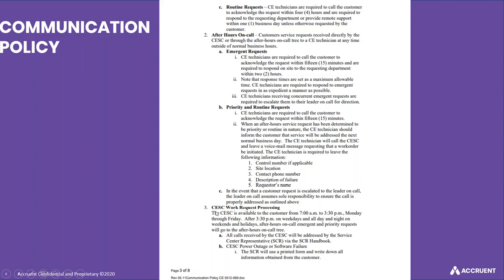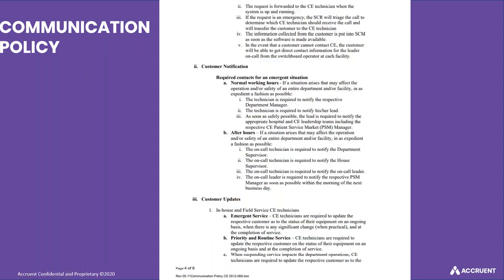And then we had a process for the clinical engineering service center where people would call in, and this was our mechanism to make sure that everything was time stamped. At the time, our CMMS didn't have the ability to do that. Our computerized maintenance management software didn't have the ability to do that. So we developed a centralized call center that everyone would call into, and they had the ability to dispatch that call to the right person. Every device in our inventory had a primary, secondary, and tertiary technician assigned to it, so that we could make sure that the right person with the right set of skills was always responding to these calls, and they were also broken out by geography, again, to make sure that the closest person got to those calls quickly.